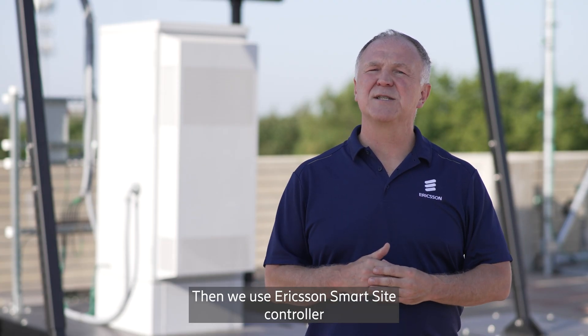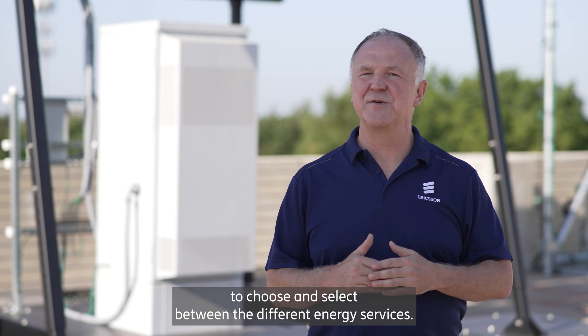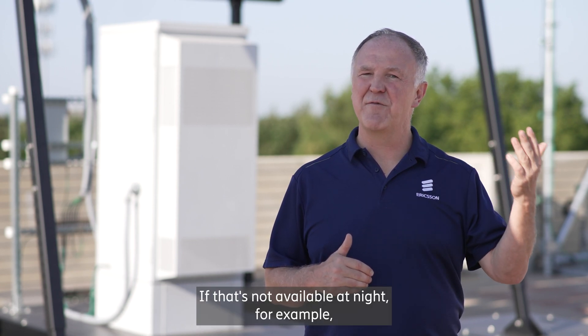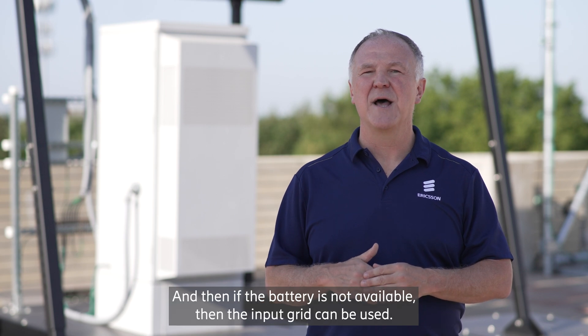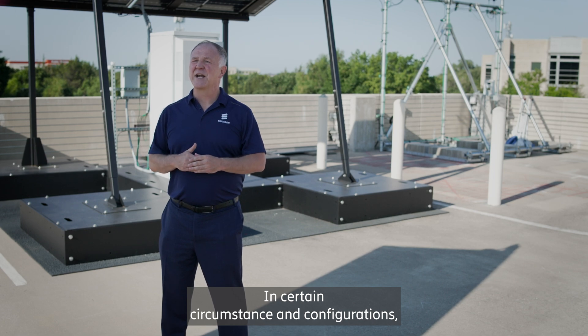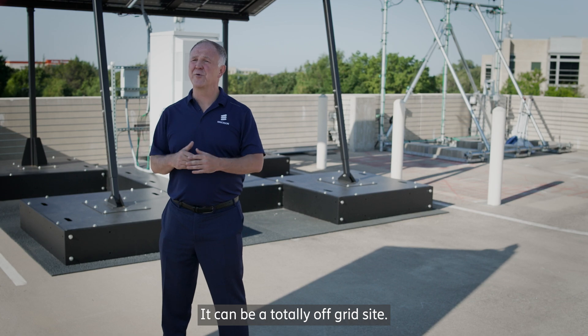We use Ericsson's smart site controller to choose and select between the different energy services. Firstly, we'd use solar power. If that's not available — for example, at night — we would then switch to the battery capability. And then if the battery is not available, the input grid can be used. In certain circumstances and configurations, we don't need the input grid at all.